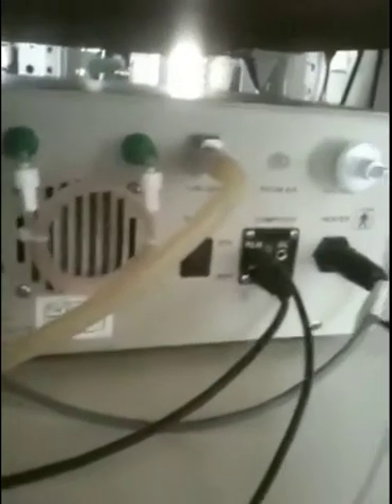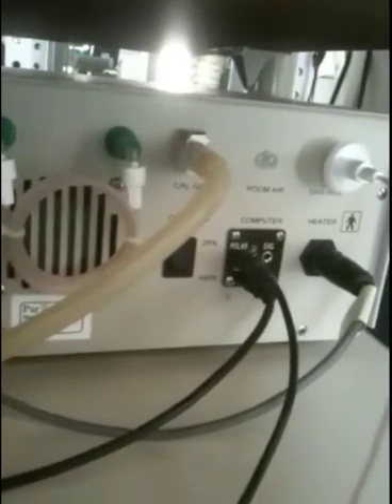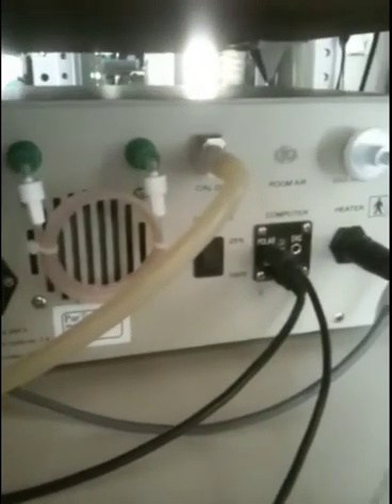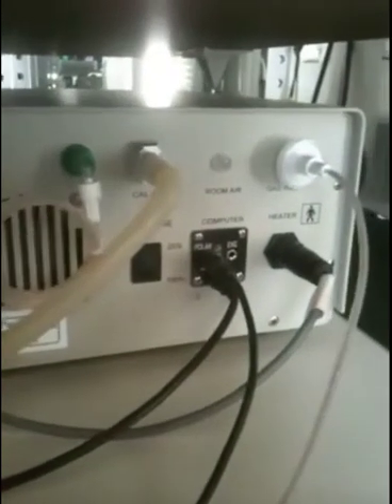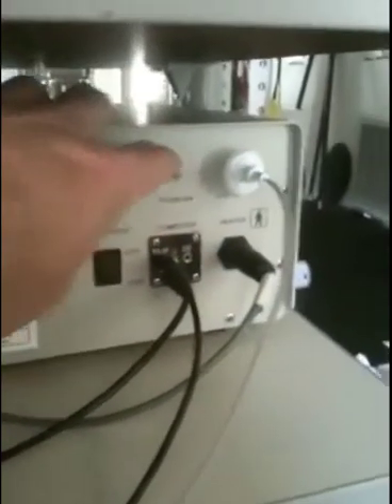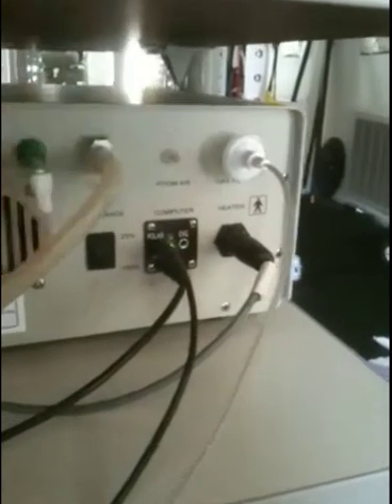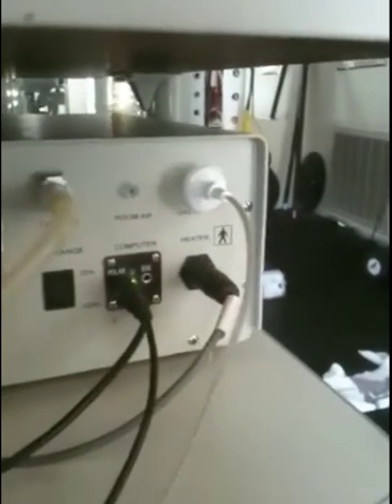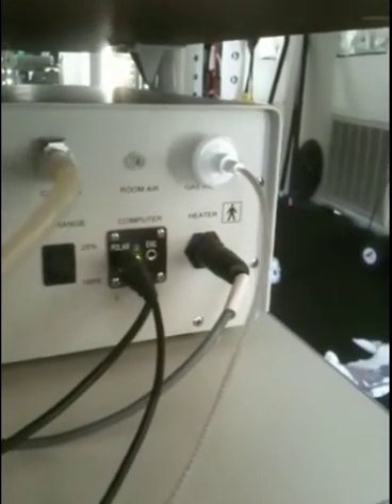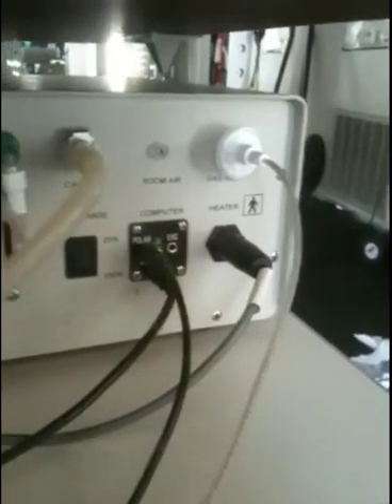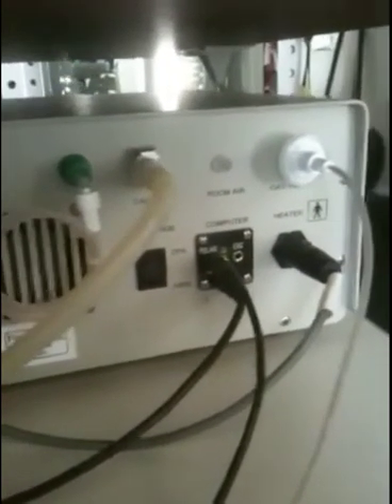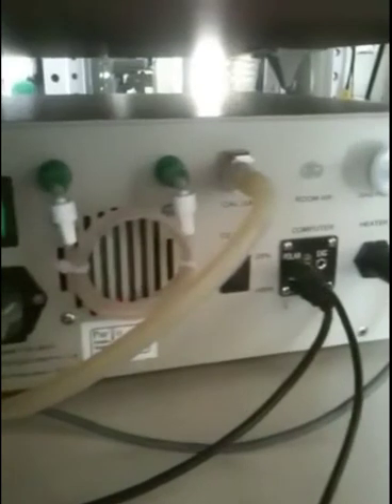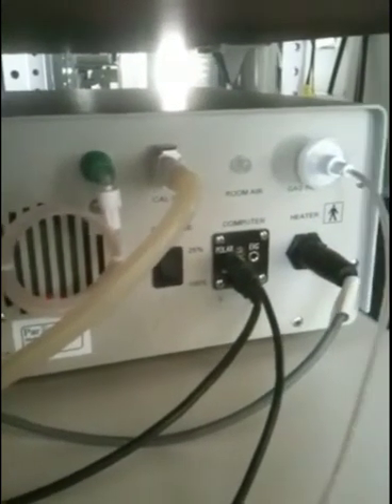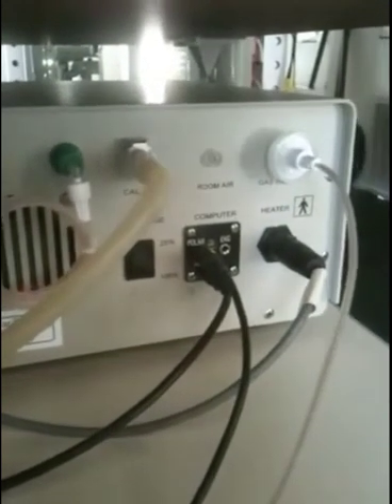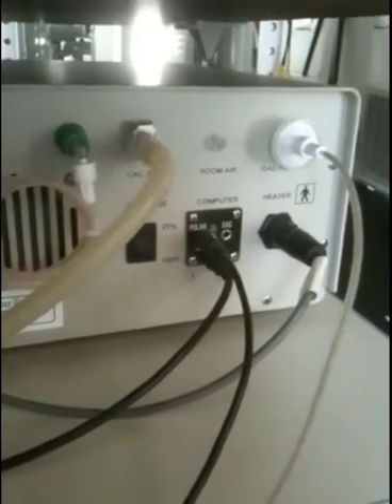So on the back side, if I show you this over here, you can see there's a clear rubber tube that goes into it. That's the calibration gases, and then there's also kind of an open gasket there that sucks in room air. So what it does is it sucks in room air, sucks in calibration gases, and just calibrates the oxygen analyzers and carbon dioxide analyzers based on known gases. So that's very accurate and reliable.